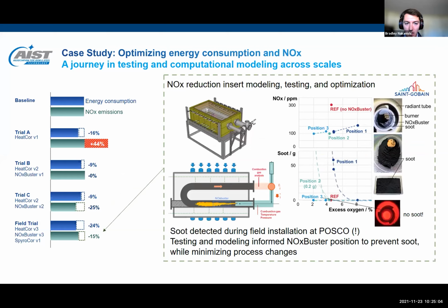Finally, I'd like to highlight how we solved a critical problem that we encountered during the field trials involving soot. Shortly after POSCO restarted their furnace installed now with total burner solutions in a single zone, they observed strange behavior requiring zone shutdown and further investigation. After removing the burners, they discovered significant soot deposits on the NOx busters in multiple radiant tubes from the zone. Not a great situation.